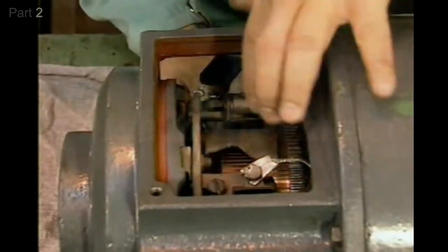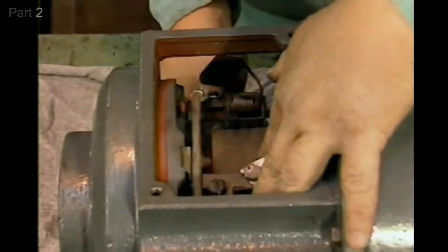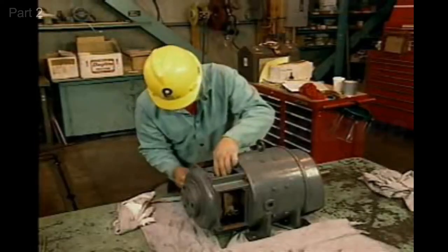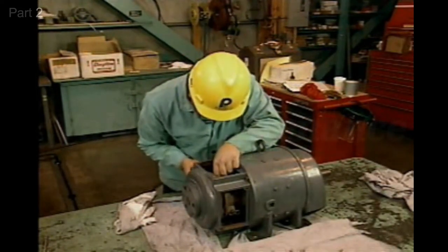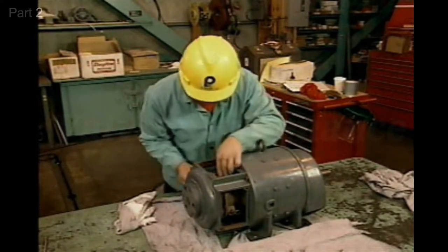The strip of flint paper is then placed on the commutator with the flint side out. The brush is placed in the brush holder and the tensioning device is adjusted to hold the brush tightly against the flint paper.